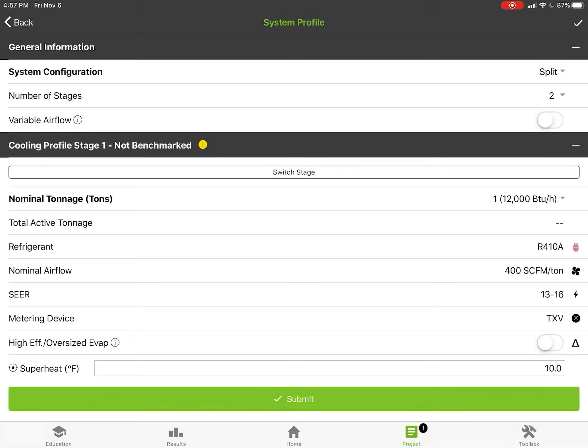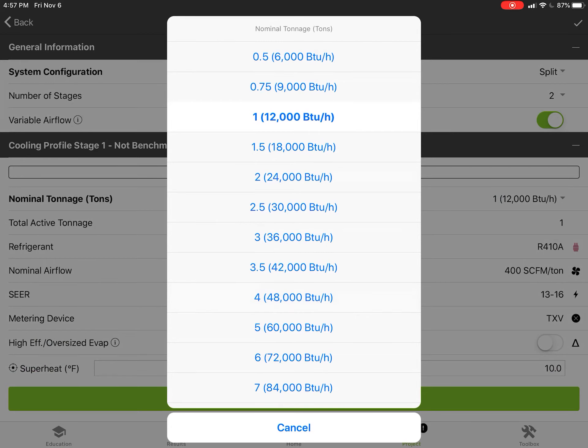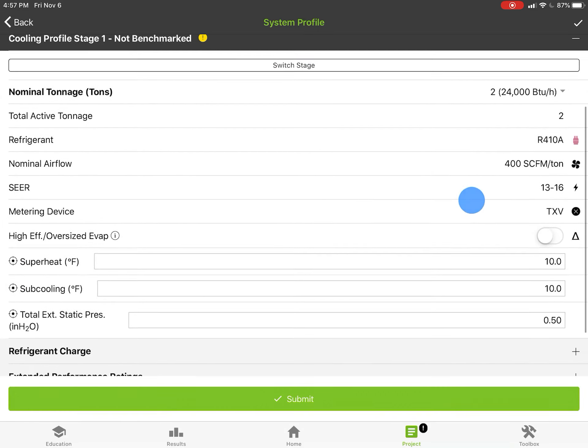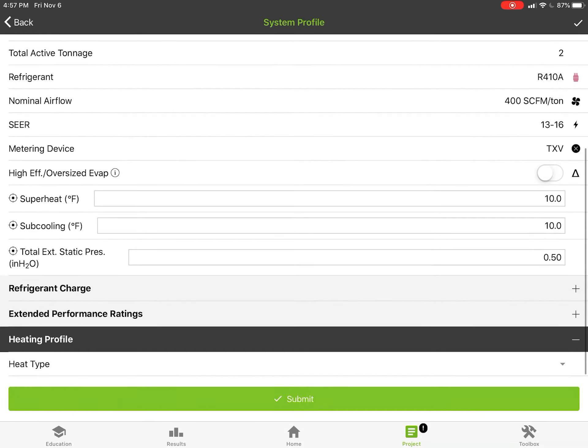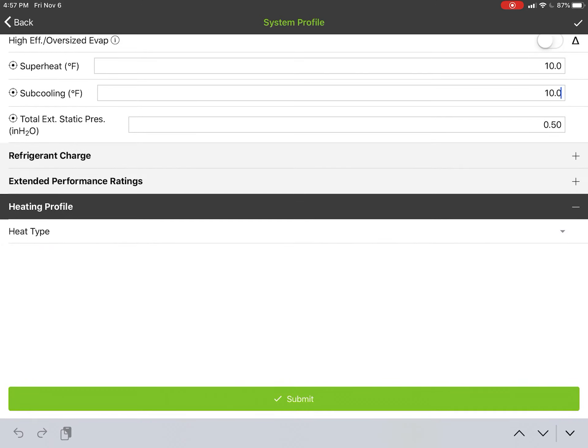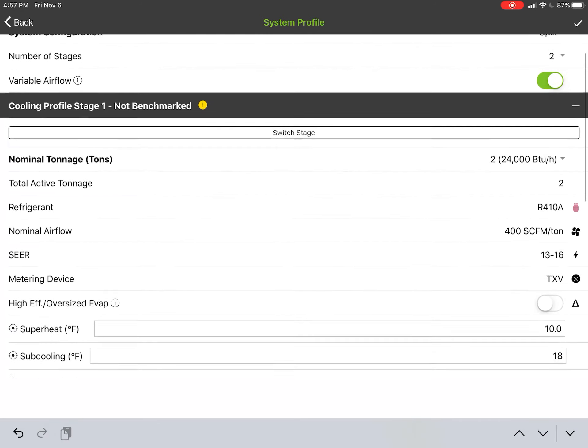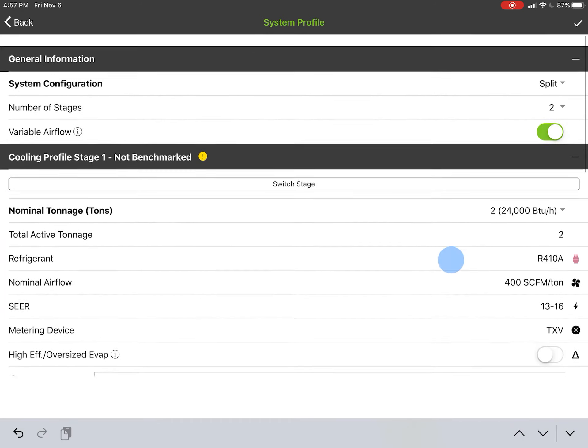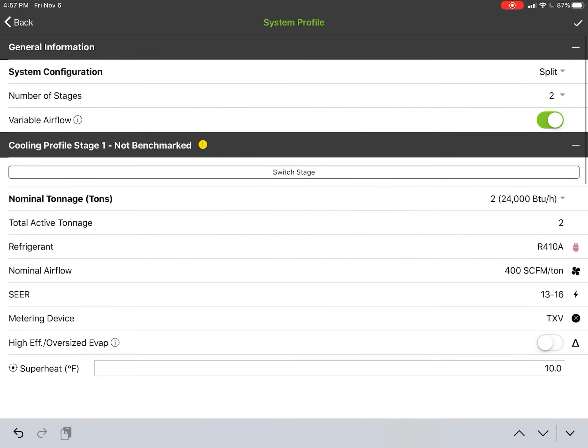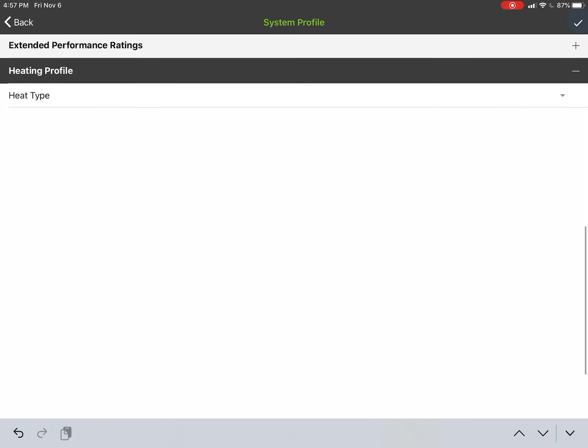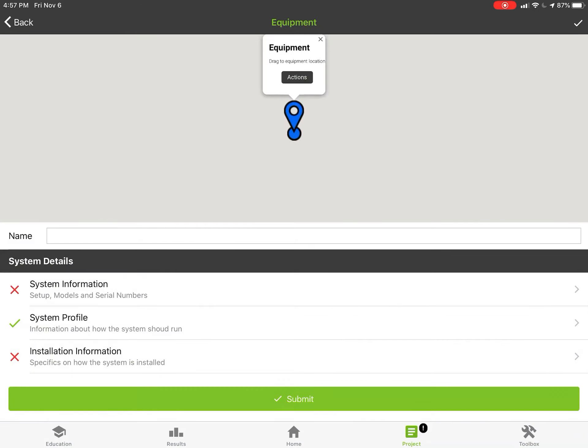a lower airflow on first stage than it does on second stage. We'll just profile it like it's my house, so it'd be a variable airflow system. My first stage is two tons, and then I've got a target subcooling here of 18 degrees on my system, and then half an inch of total external static, TXV. We can go ahead and hit submit for this one.